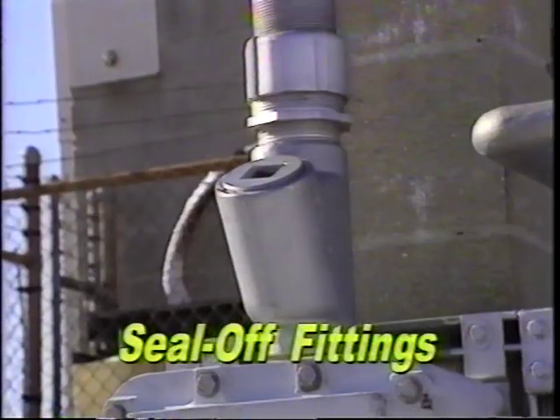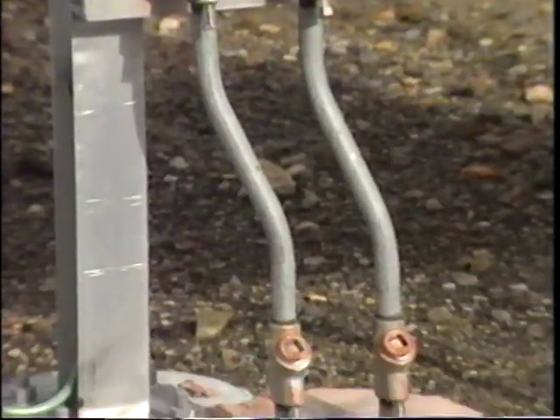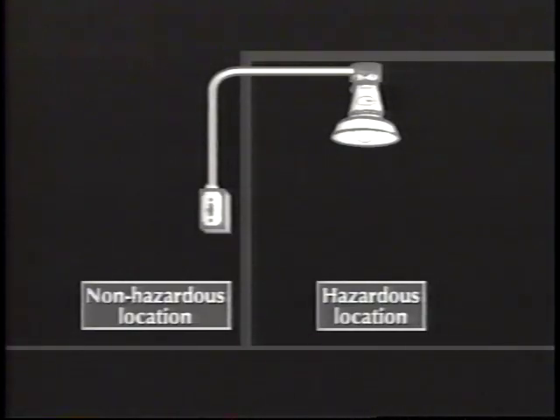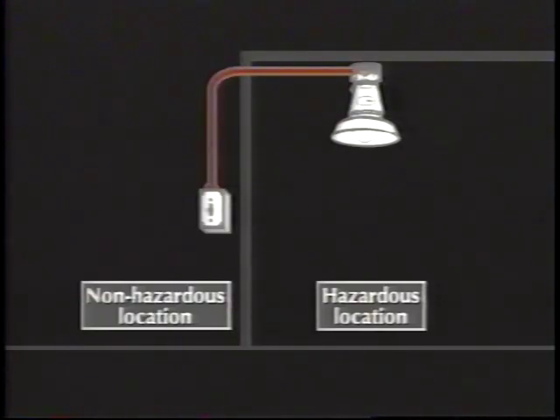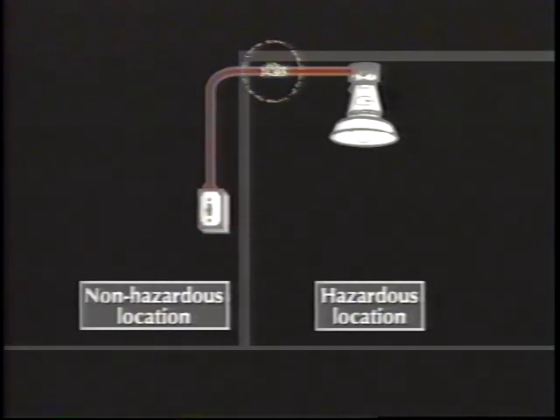Seal-off fittings are one of the most important hazardous area safety products. They work to contain explosions and minimize the passage of flames, gases, and vapors in conduit. In some cases, explosion-proof equipment is connected by conduit to non-explosion-proof equipment located in ordinary or non-hazardous areas. Flammable gases or vapors can get into the conduit and follow it back to the non-explosion-proof equipment, potentially causing a fire or explosion. Properly installed conduit seals control this hazard. Often equipment is factory-sealed. The NEC and the Appleton Code Review Booklet provide further details on where and how seal-offs must be used.